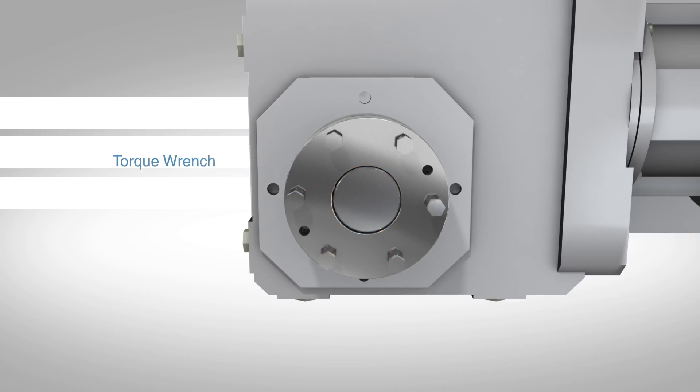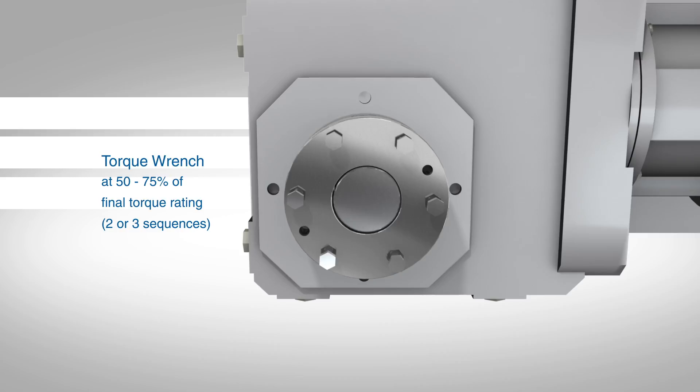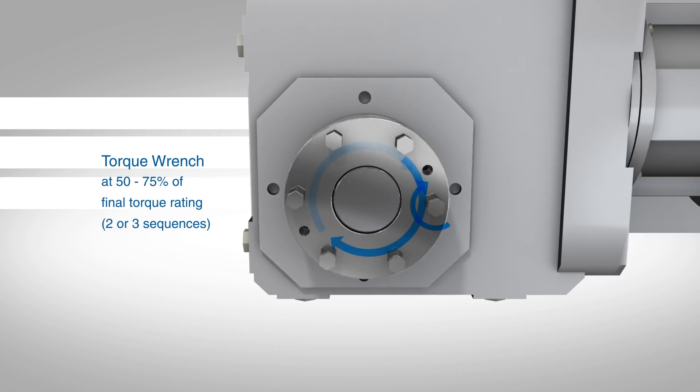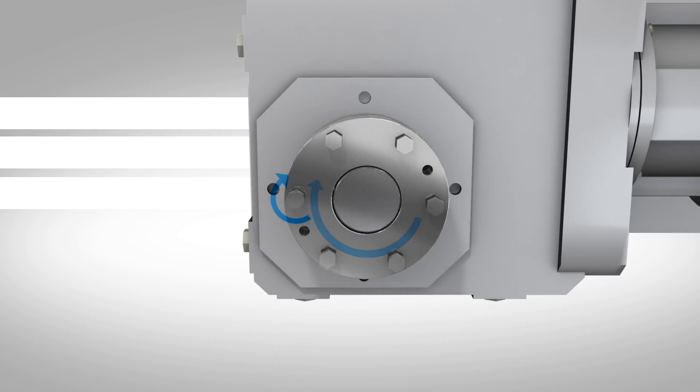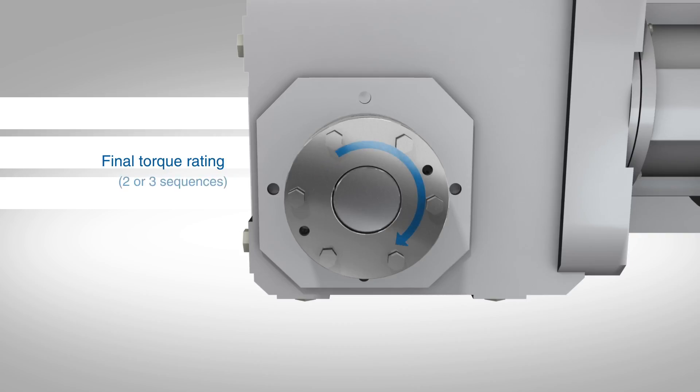Use a torque wrench to finish tightening. Set the torque wrench for 50 to 75 percent of the final torque rating. Torque the bolts at this setting for two to three rotating sequences. Set the torque wrench for final torque rating and torque for two or three more rotating sequences or until all bolts are at the same torque.